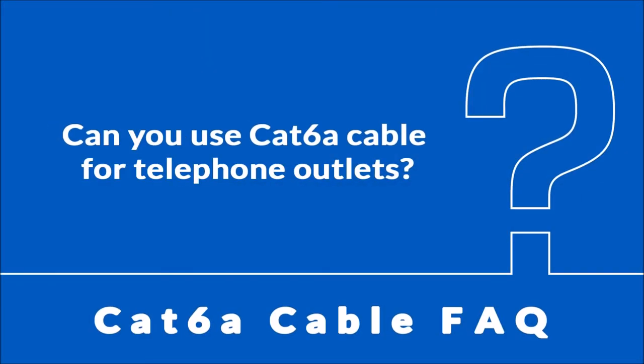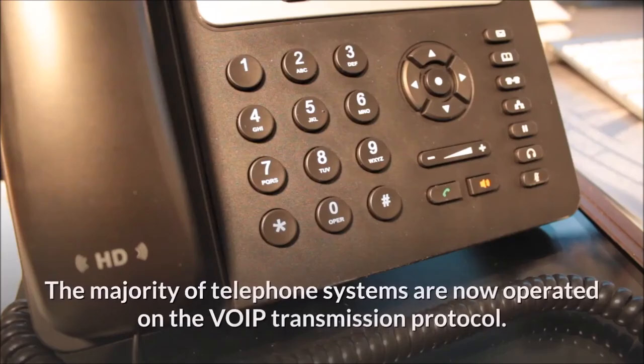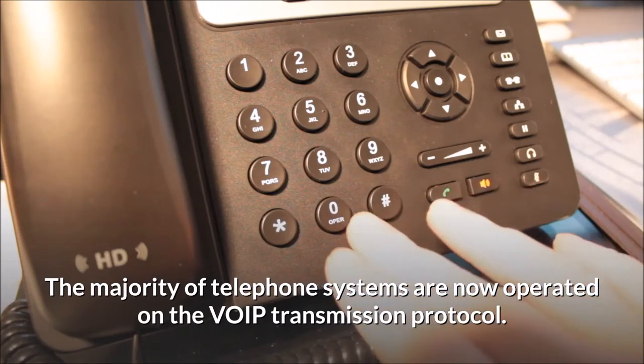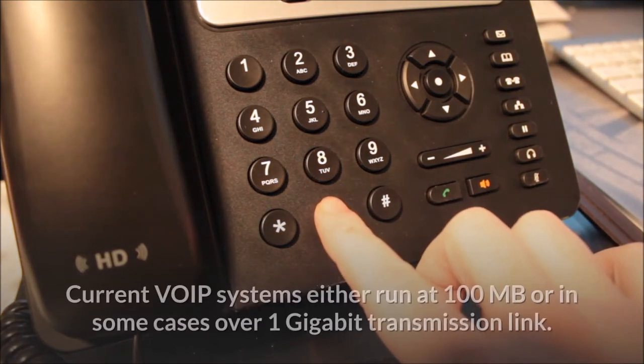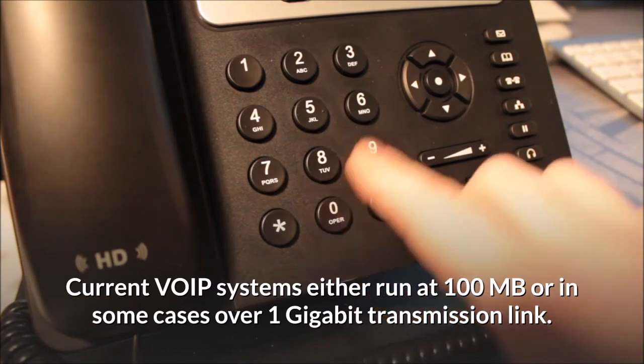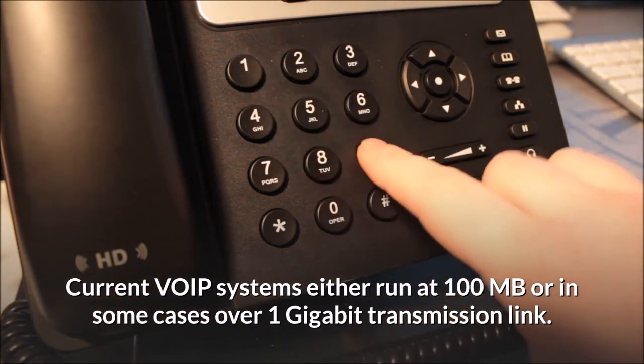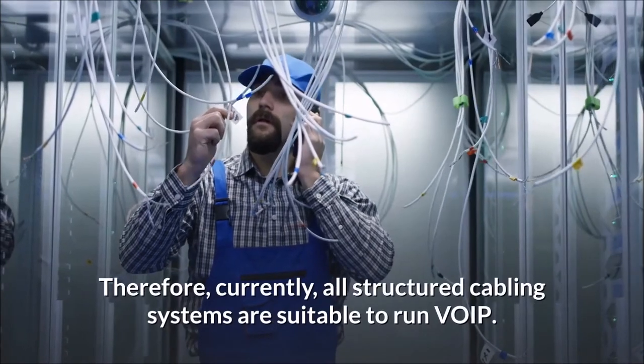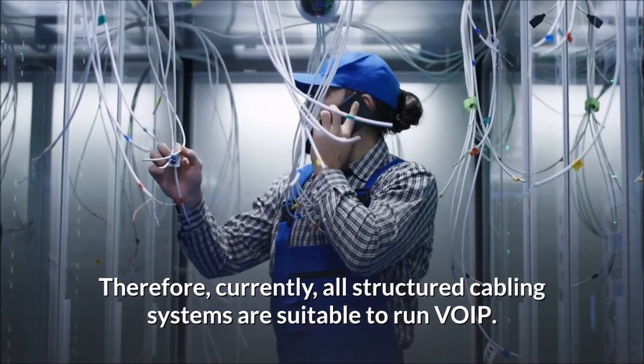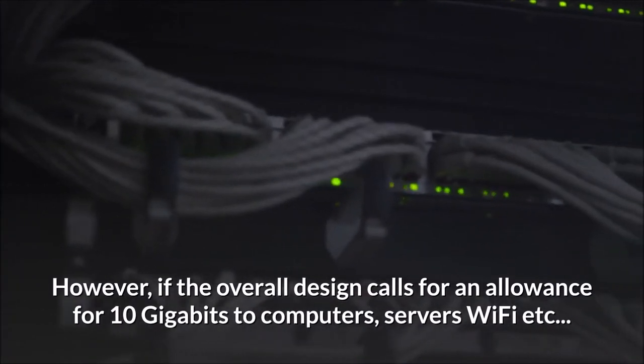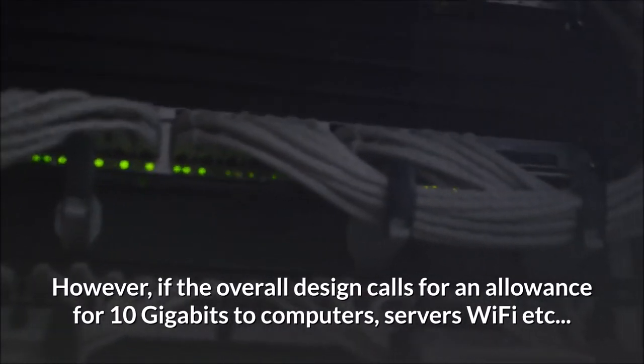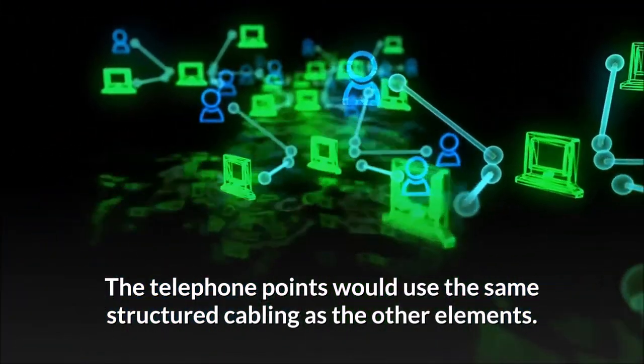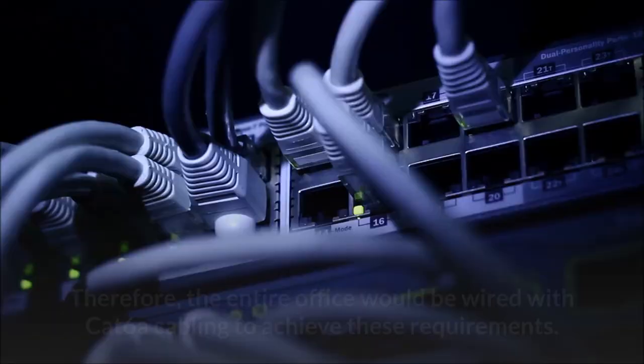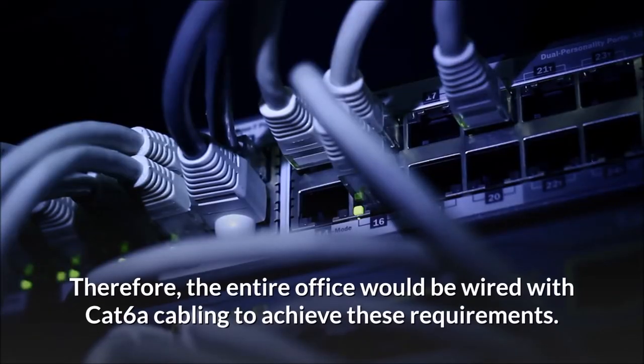Can you use Cat6a cable for telephone outlets? The majority of telephone systems are now operated on the VoIP transmission protocol. Current VoIP systems either run at 100 megabits or in some cases over a 1 gigabit transmission link. Therefore, currently, all structured cabling systems are suitable to run VoIP. However, if the overall design calls for an allowance for 10 gigabits to computers, servers, Wi-Fi, etc., the telephone points would use the same structured cabling as the other elements. Therefore, the entire office would be wired with Cat6a cabling to achieve these requirements.